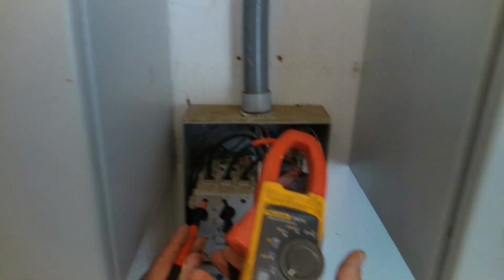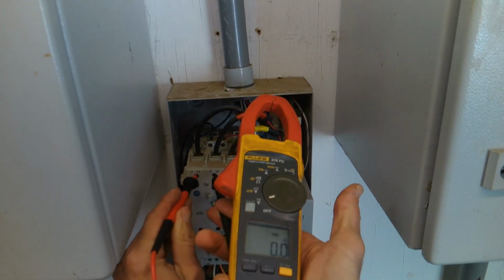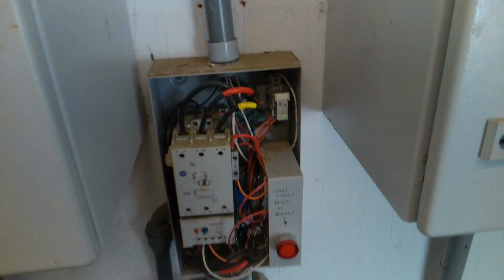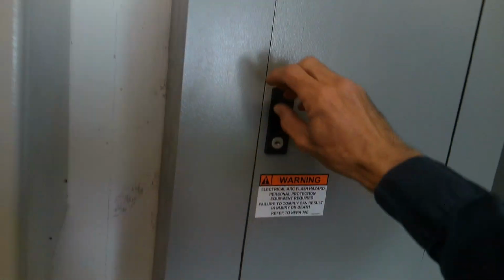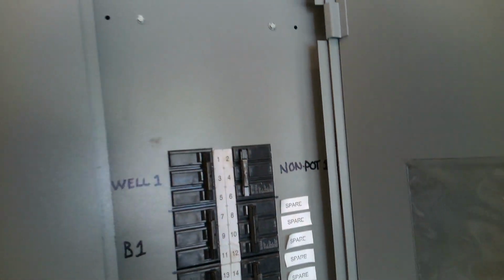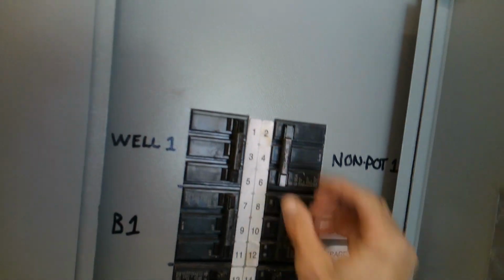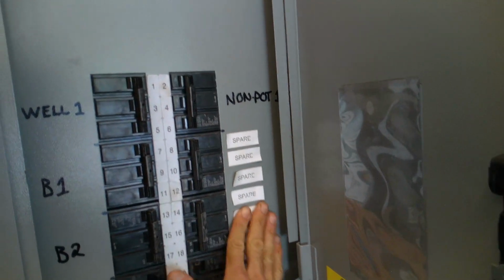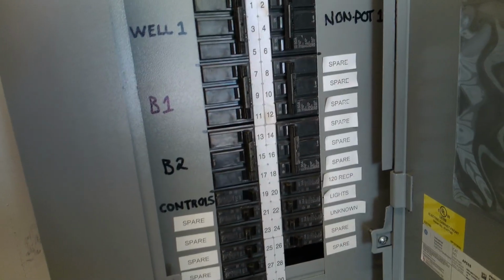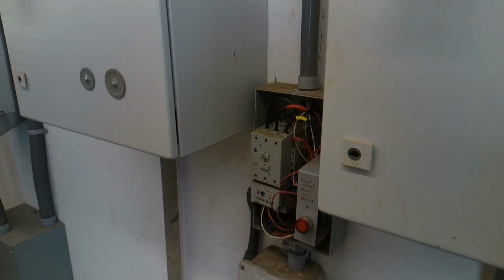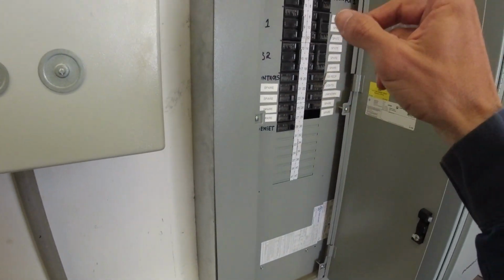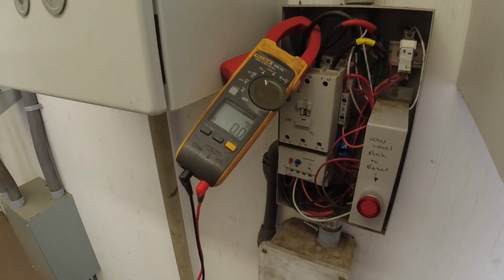Okay, so contactor is sucked in. We have voltage. We have no voltage. We have control voltage. Breaker is tripped. And look at all these falling off. So we've got no voltage on top. Breaker feeding it is tripped. We're going to reset the breaker and see what the amps do.